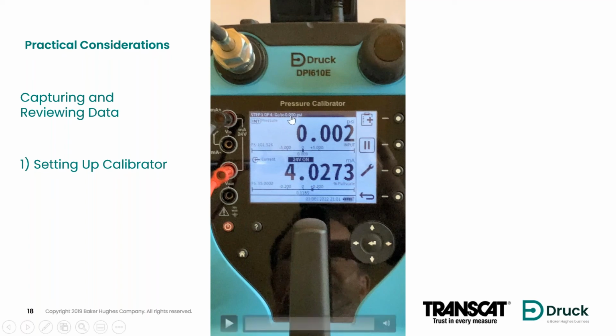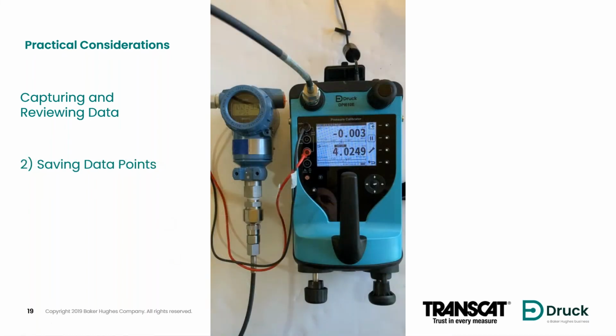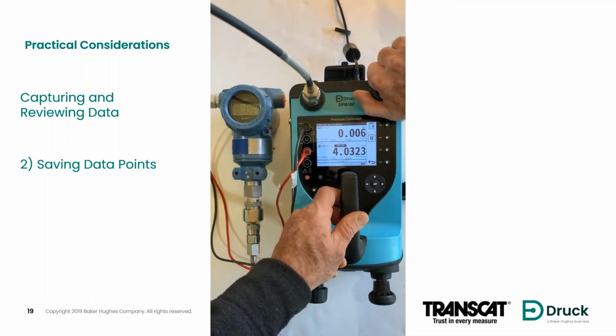You'll see up at the top of the screen here, and I'll point this out in the next one as well, that it tells you or gives the operator direction as to what pressure they're supposed to be applying. So I'm going to go on to the next screen, and here you'll see that we have the calibrator connected to a different device, more of a process style transmitter that some of you may be used to or familiar with. So I'm going to do the test. The first thing that I'll do is I'm pointing out that I need to go to 0. So that's the button that I would push to save that point. It actually showed me that it was out of tolerance, and it asked me if I still wanted to take the point, which I did.